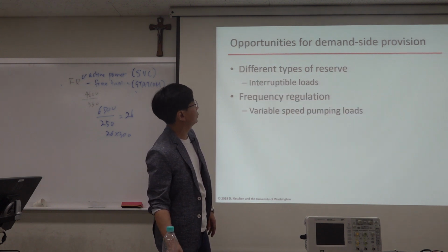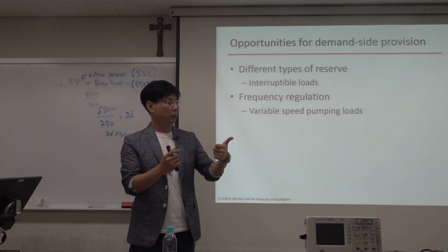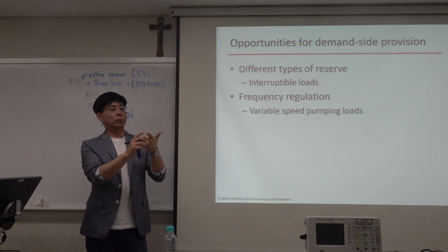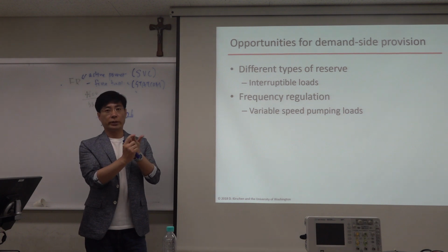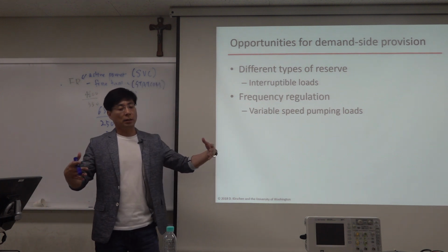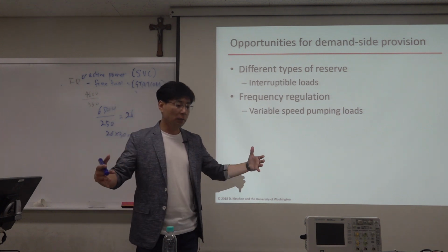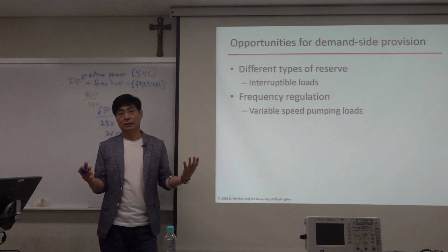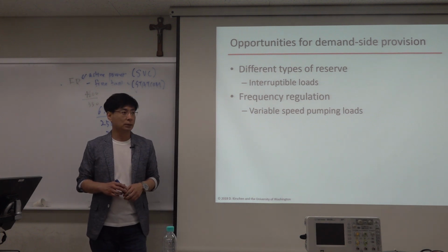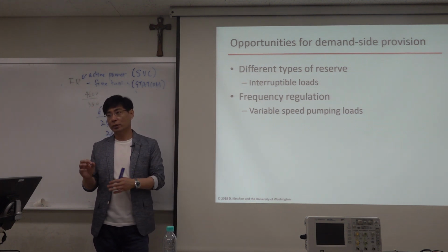And so there are two types of DR services. The first one is based on the DR capacity, and the second one is actual reduction of the demand when required. Okay, so as a DR provider, you can say, hey, I have this amount of capacity. Here the capacity means the capacity of reducing the consumption. I have this amount of capacity measured in megawatt. You can get money even if you do not actually reduce your load. But when a DR event happens, you must reduce that amount of load.